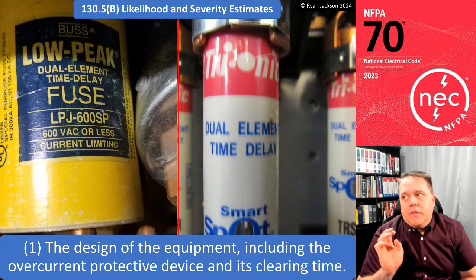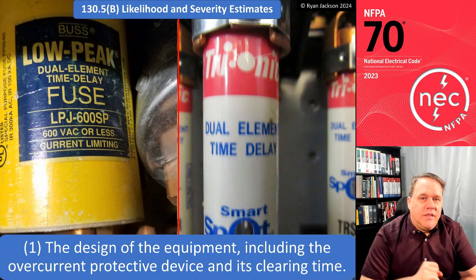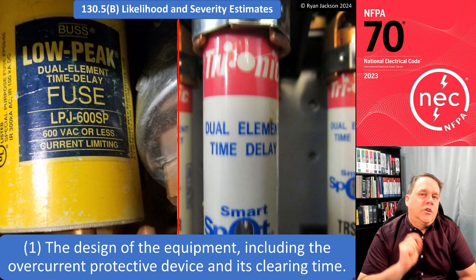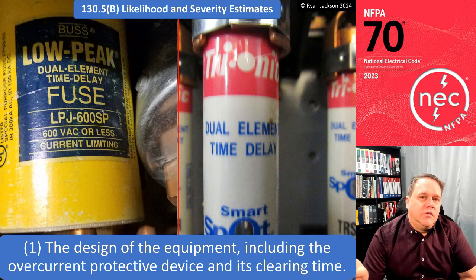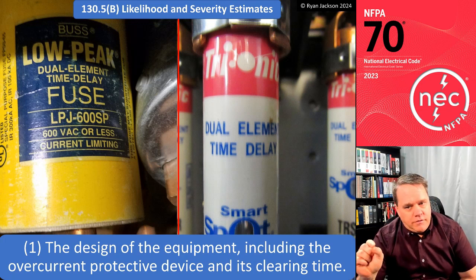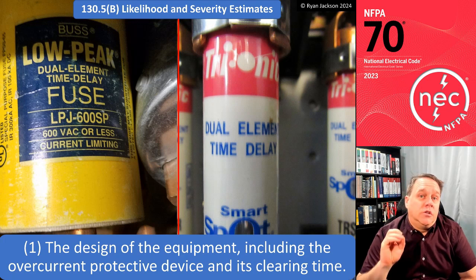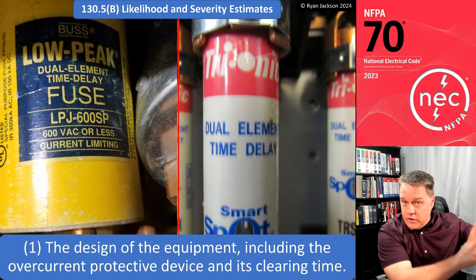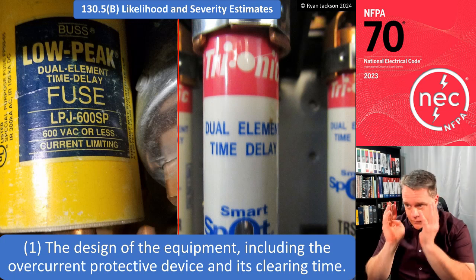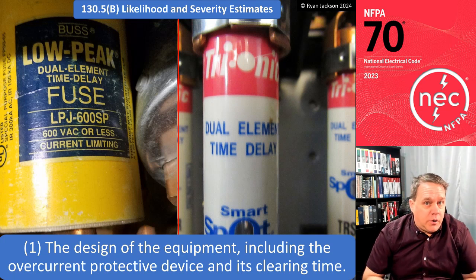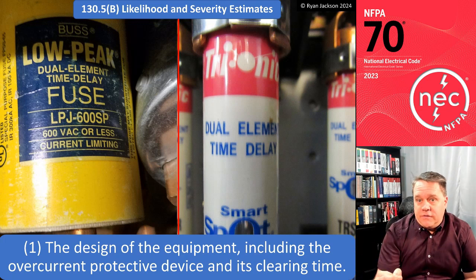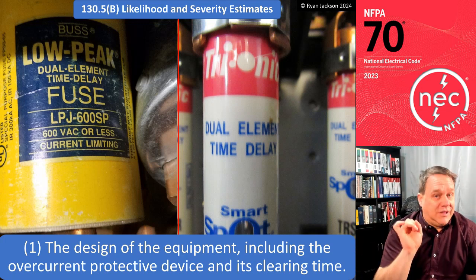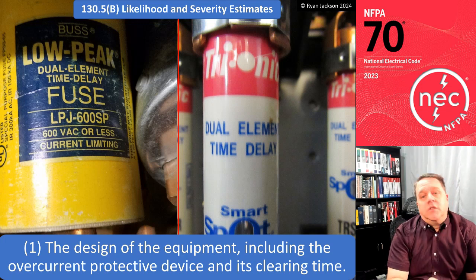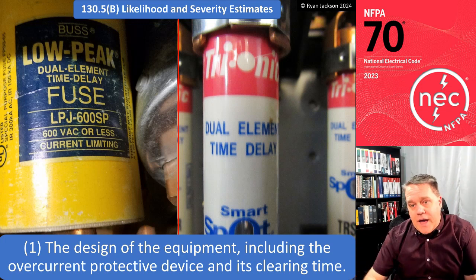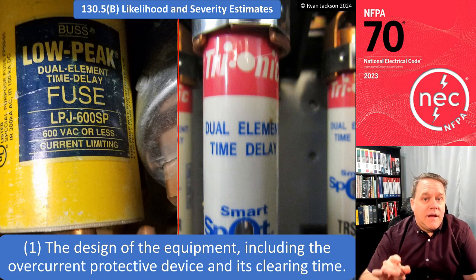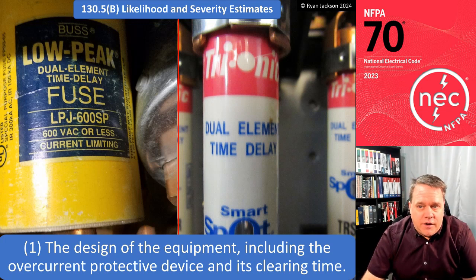Number one, you need to consider the design of the equipment, including the overcurrent protective device and its clearing time. There is a big difference between these two fuses. All right, the fuse on the left is a current limiting fuse. The fuse on the right is not a current limiting fuse. The current limiting fuse is going to result in a much lower incident energy, right? With everything else being equal, right? The fuse on the left is going to have a faster operating time, which is going to decrease the severity. Is that going to decrease the likelihood? Probably not, but it's going to decrease the severity of something bad happening. So we need to consider the design of the equipment and the overcurrent device and its clearing time.